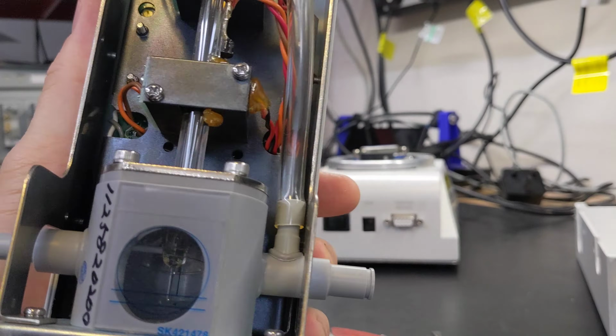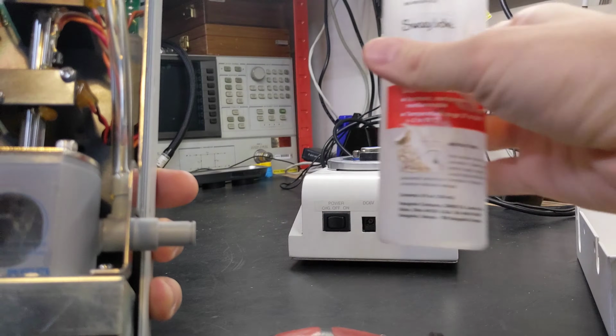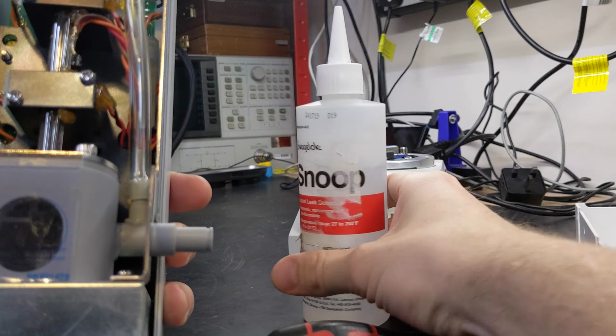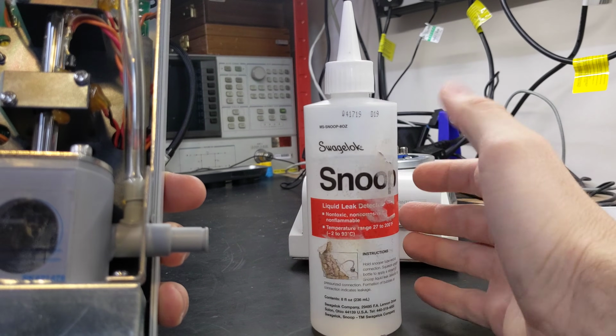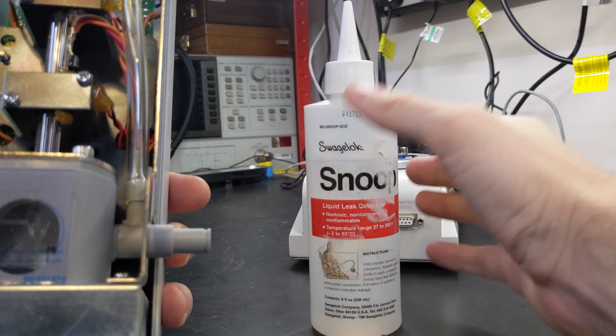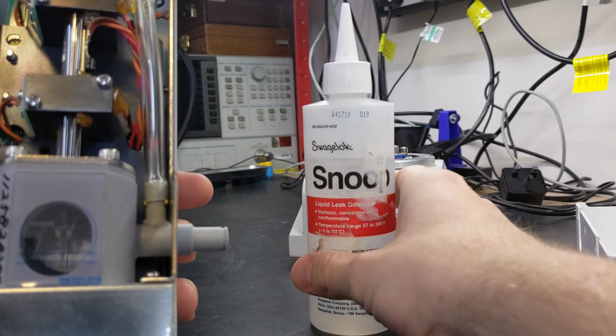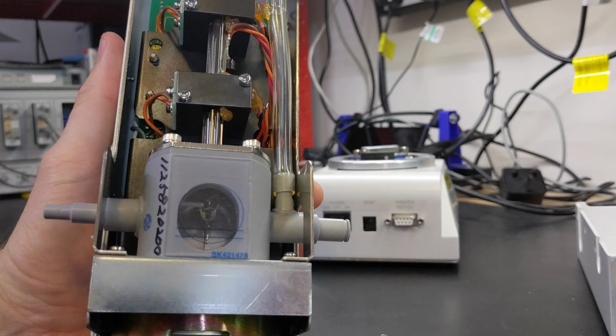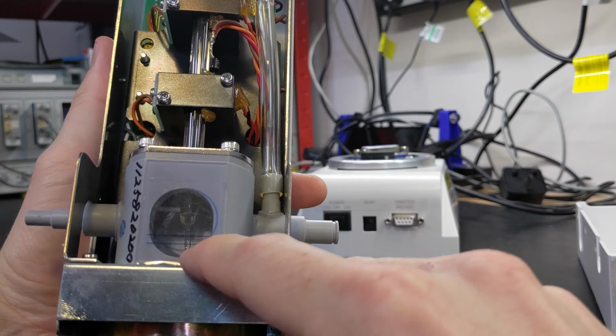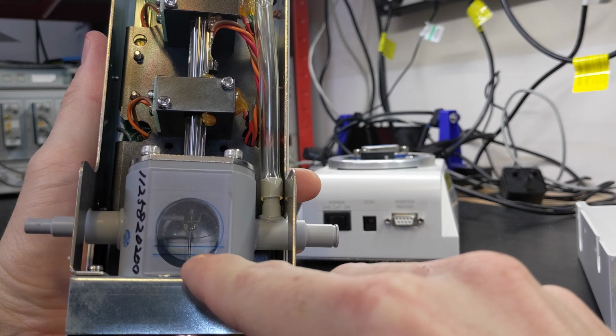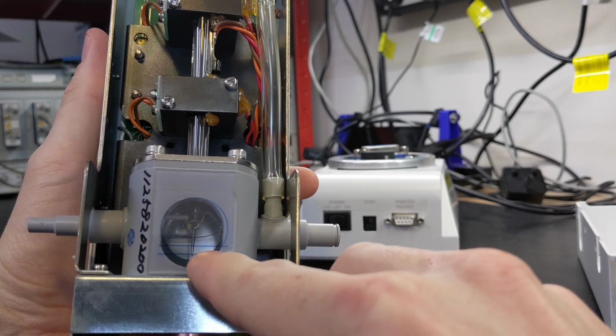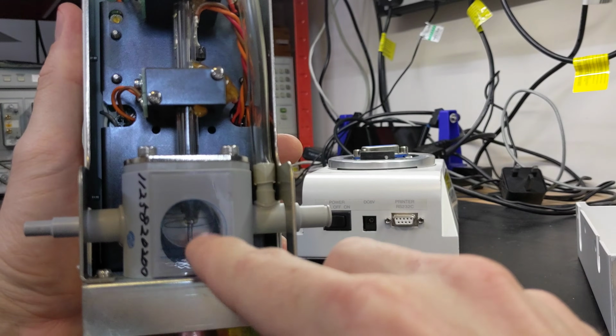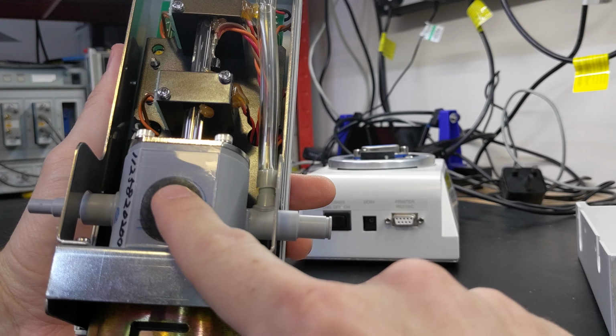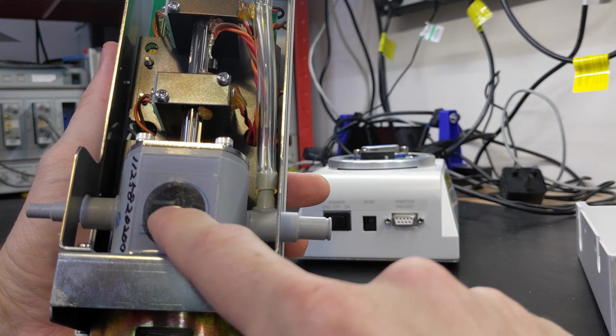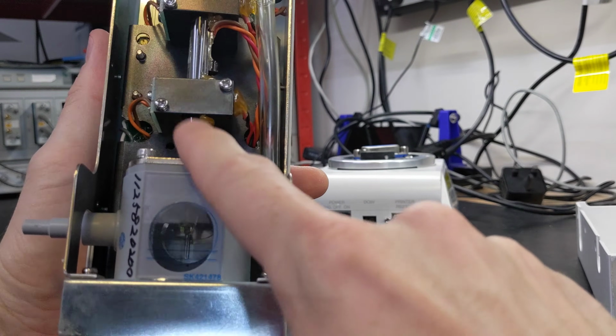For these types of meters, what you're meant to use is this Swagelok Snoop liquid leak detector - it bubbles like mad but is also non-toxic, non-corrosive, and so on. You fill this bottom chamber with Snoop, and the small metal loop will dip down, create a bubble inside of it, then pull it over that spike. The spike is shaped so it doesn't burst that film while the bubble's being dropped over it.